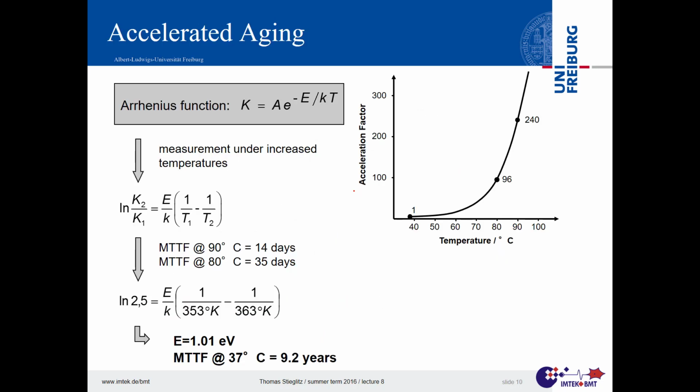So there was one thing now with the materials and the thickness. If I want to get an implant that I get now, and my life expectancy is hopefully another 25 or 30 years, I want to be sure that this device lives that long. Or at least I want to get a certificate that tells me this device lives for 10 years, right? If I would be the manufacturer, I would have to prove that.